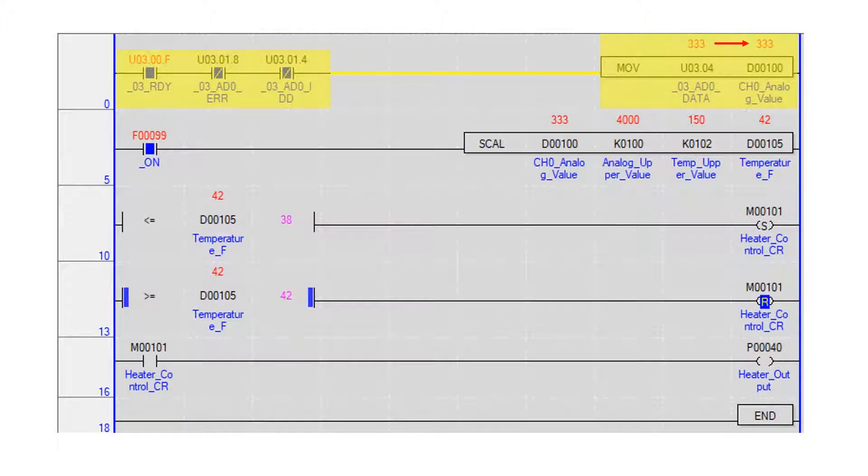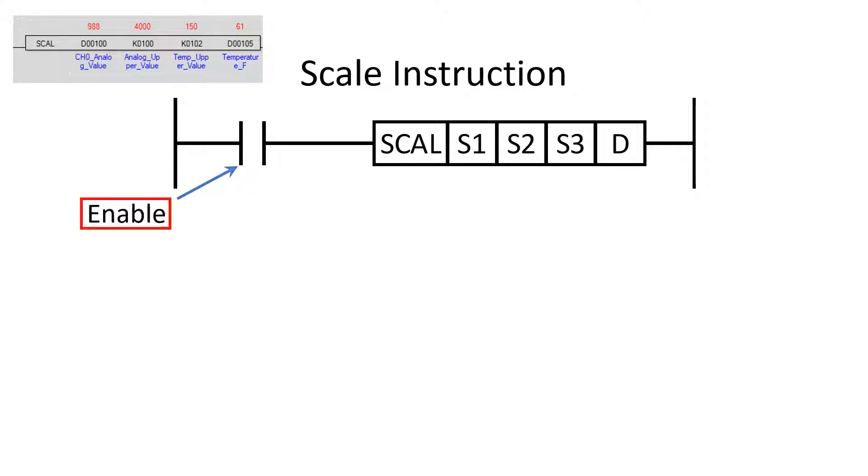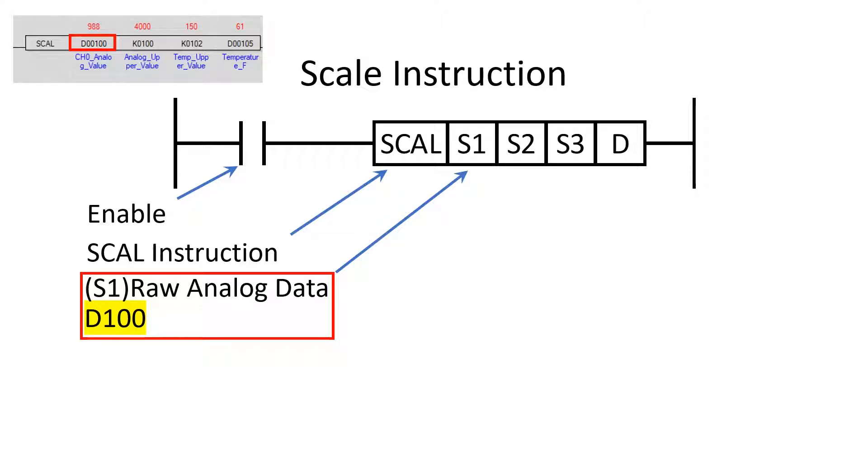In this example, the always on bit in the PLC enables the scale instruction. An enable condition is required when using the scale instruction. This program uses the SCAL instruction. Operand S1 stores the raw analog data. In this program, it is D100.